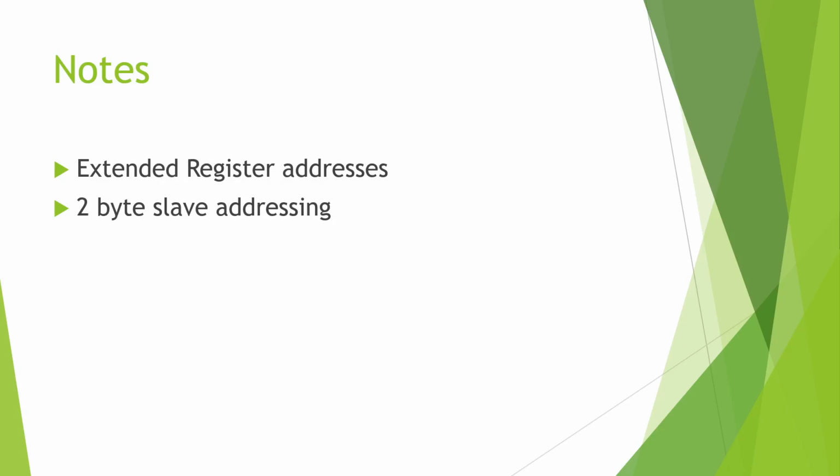Why would you need 65,000 different devices on your network? I have no clue. That one makes absolutely no sense. But maybe you do, or maybe you just need like 255 devices and you can't do it with the base one, so you say, we need a few more, let's go 2 bytes. By default, simple Modbus software only uses 1-byte addressing. As soon as you go greater, it will automatically switch to 2-byte if your system supports that capability. So something to be aware of.